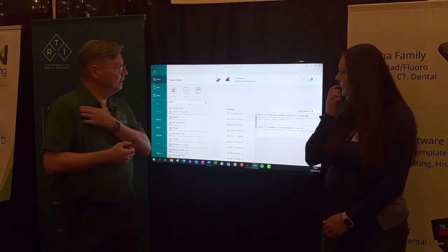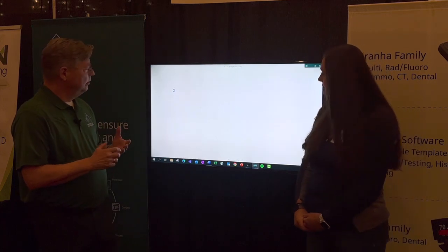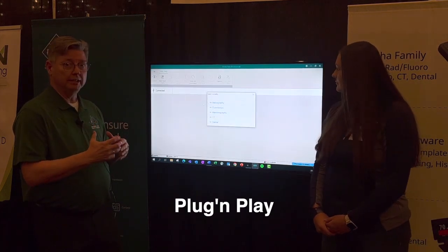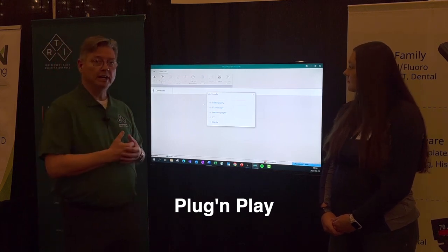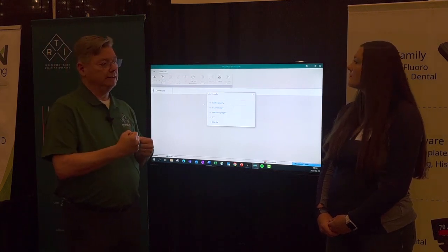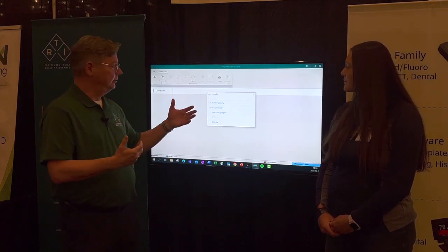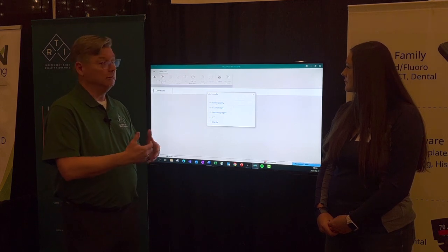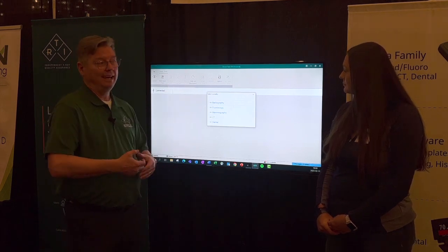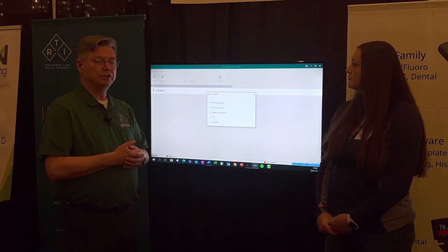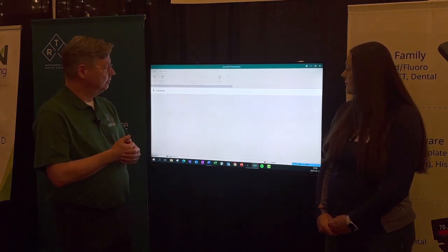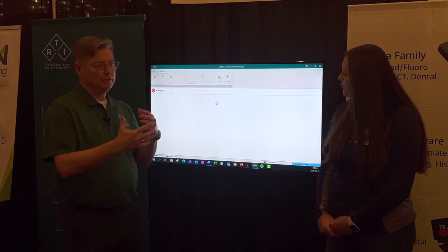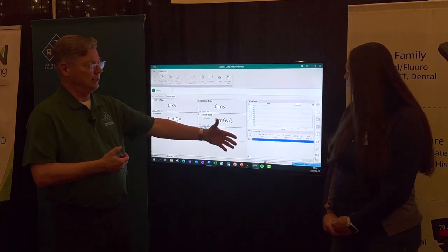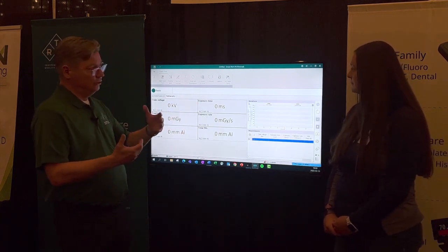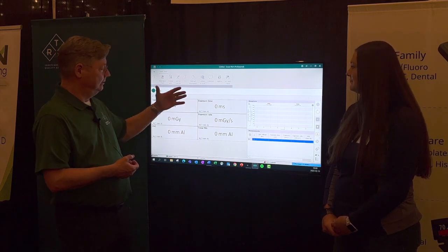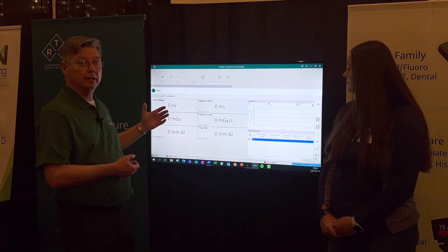So the first one we'll have a look at is the quick check, which is a kind of plug-and-play functionality where the software will communicate with whatever instrument we have attached. Depending on the configuration of that instrument, it will ask questions. What do you want to do now? What we have attached now is a Piranha Multi, which can do radiography, fluoro, mammo, CT, and dental. So we need to decide which configuration we'd like to have. Say we want to try radiography. The software will then configure itself and pull up a view that gives us as much information as we can. Like I told you before, we have from the Piranha the kV, time, dose rate, total filtration, and HVL all in one shot.